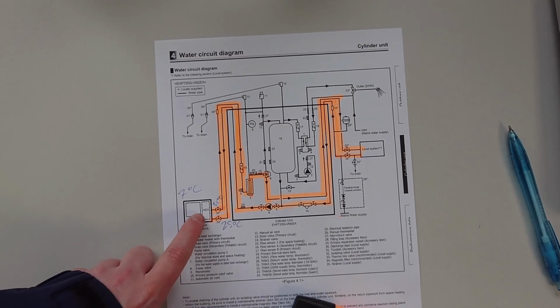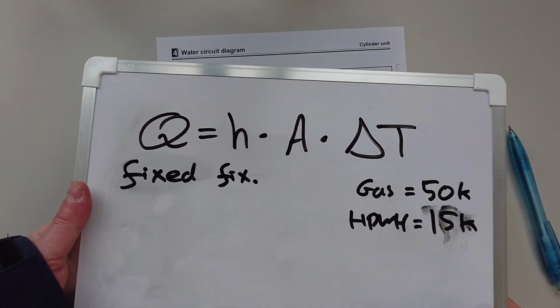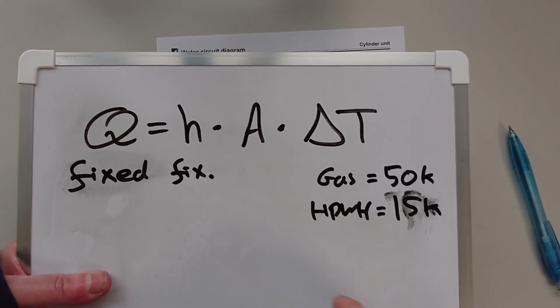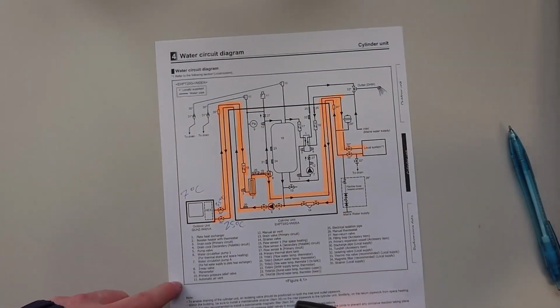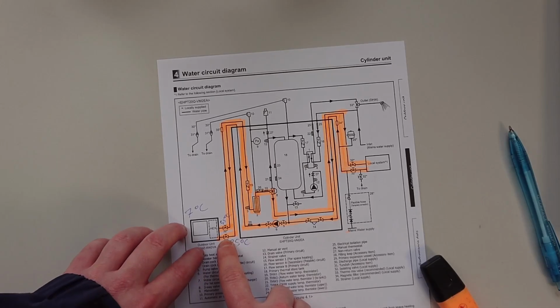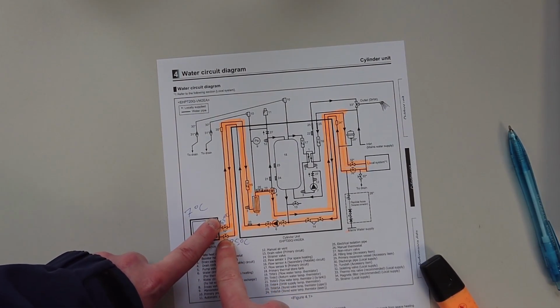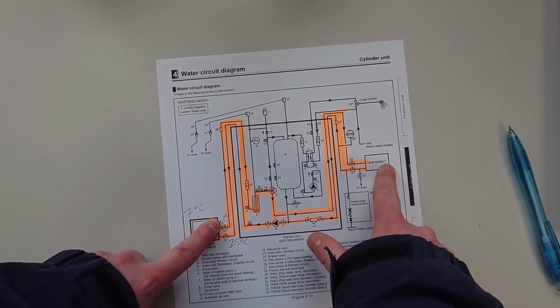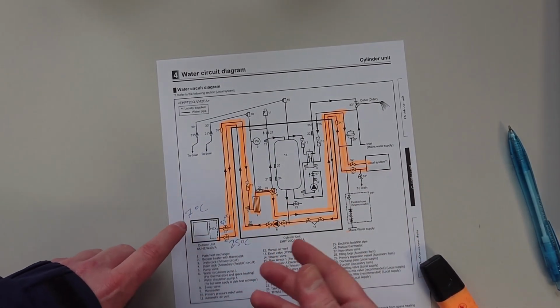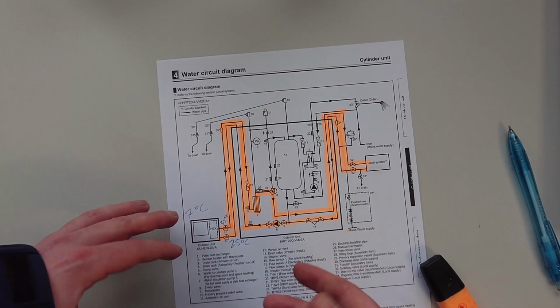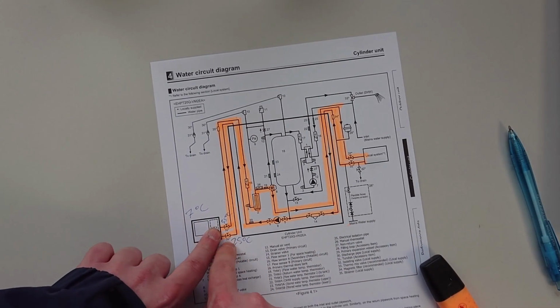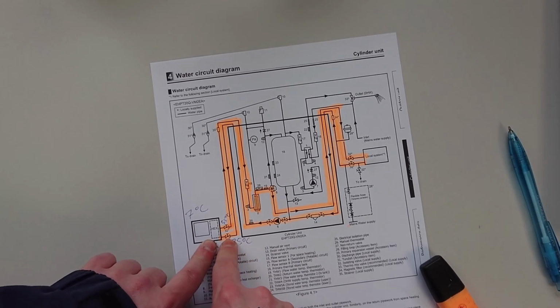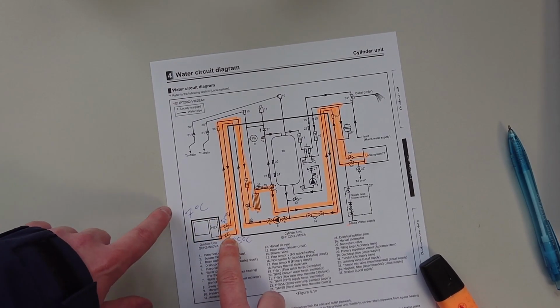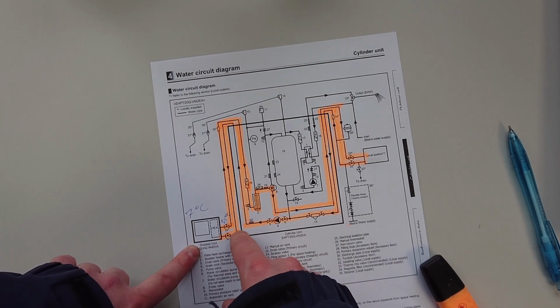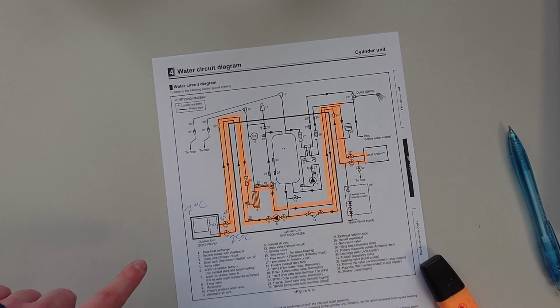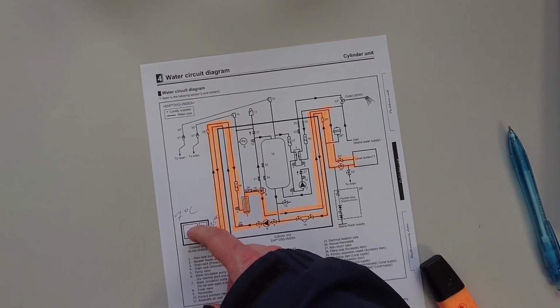Now, quite interestingly, you look at this and you say, okay, fine, why don't we increase the delta T so that we don't need the radiator to be as big? Okay, let's try it. So we're going in here, and we need to raise this above 35 so that we have a bigger differential when we get over here. And remember, your test point where you're rating, when you read whatever the COP of your heat pump is on the packaging when you buy it, is rated here. They're measuring it, saying we've got 25 water going in, 35 water coming out, and we've got this much mass flow, and therefore we know that's what the COP of the system is, based on how much heat we put into here.